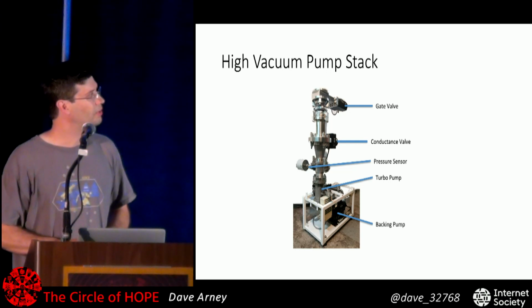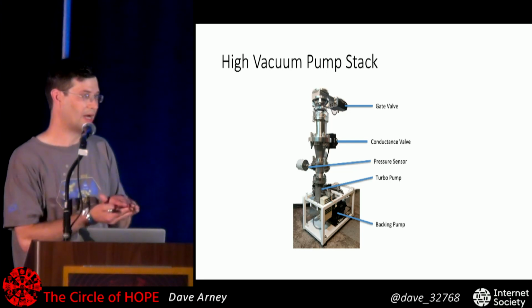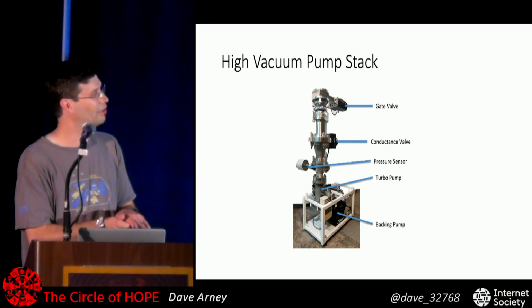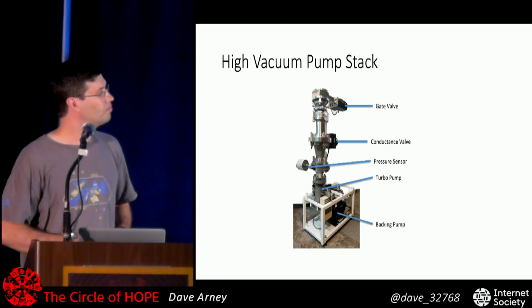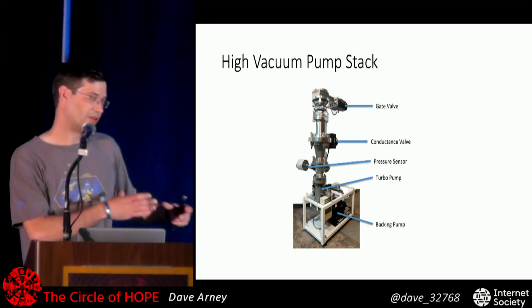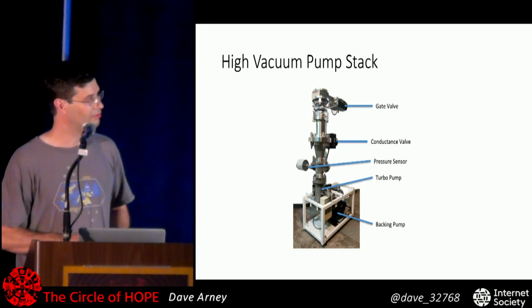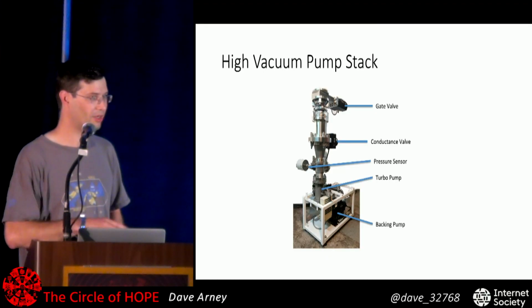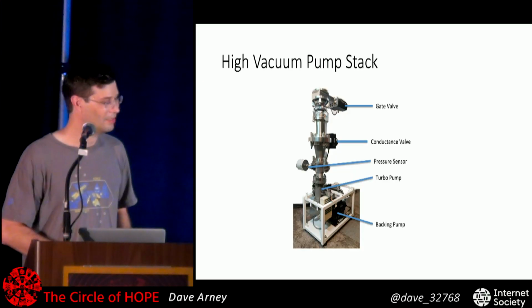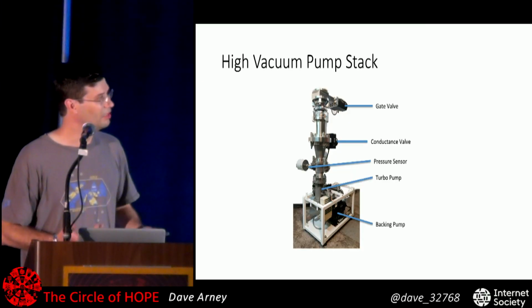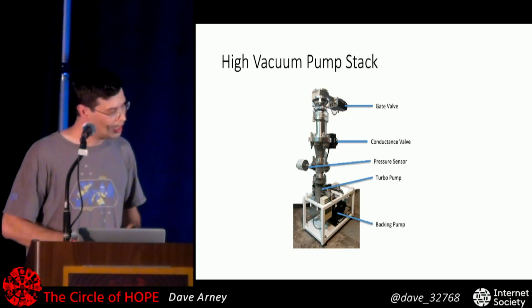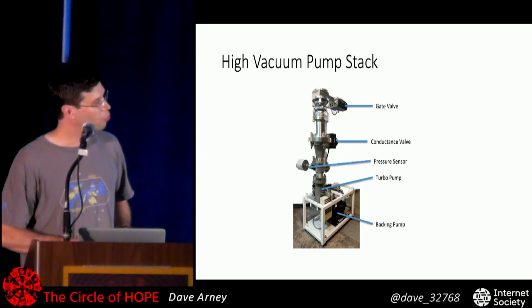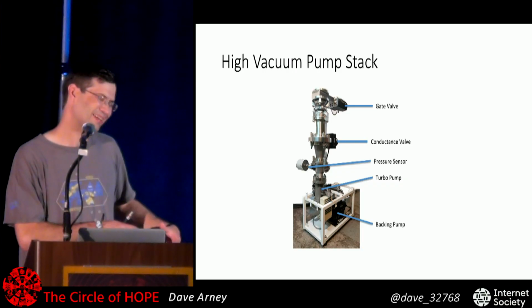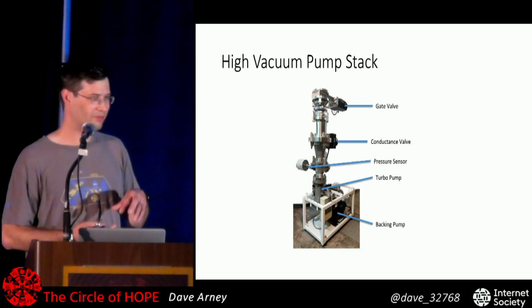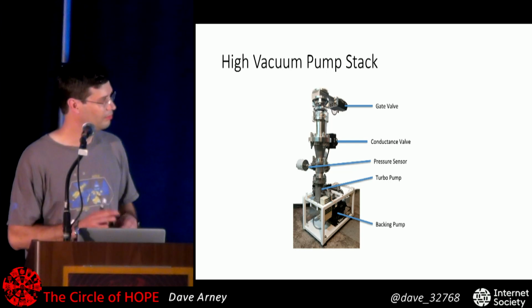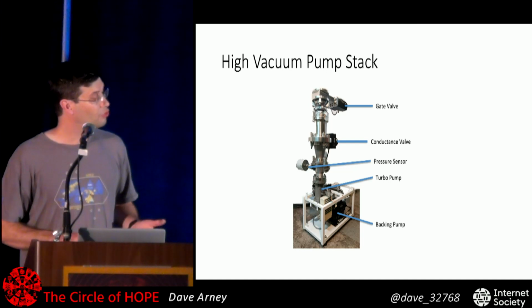And then there's a gate here, because the gate valve is just like an on or off, can allow gas to go through or don't. And that's used to separate off the plasma chamber from the rest of the system, so they can leave this pumped down or purged with dry nitrogen to keep water vapor from getting in, because it's humid, because it's my basement. The high vacuum pump will only work if it's already in a vacuum. It has some vanes that spin really, really quickly. We'll get to that. I've got some pictures. So it already needs to be in a vacuum.